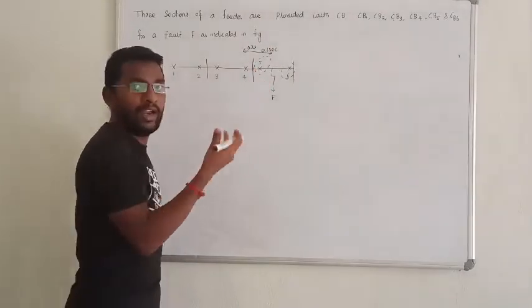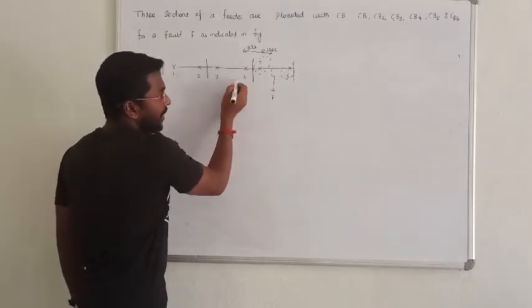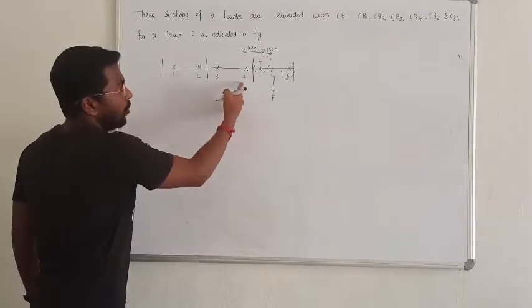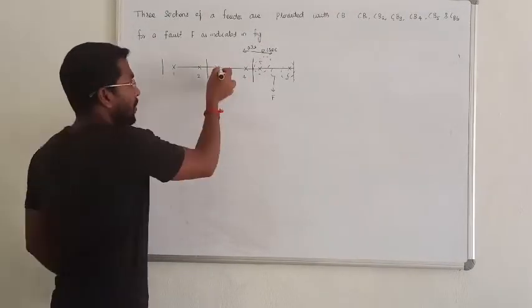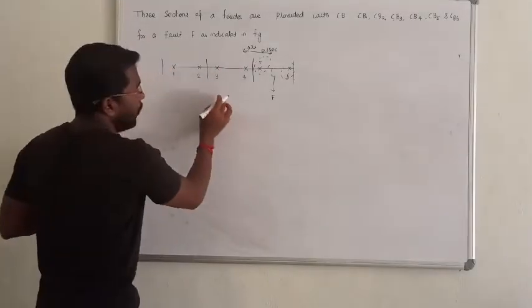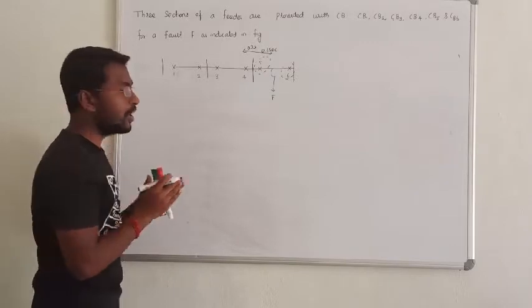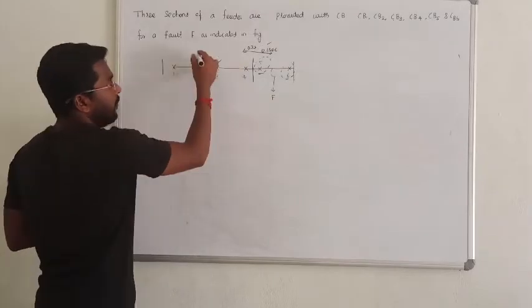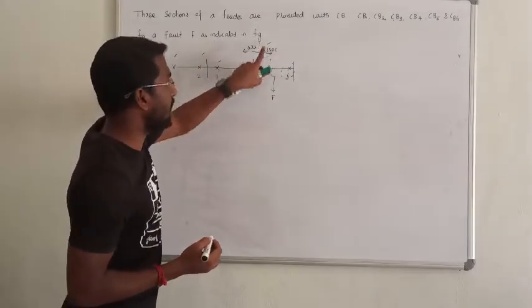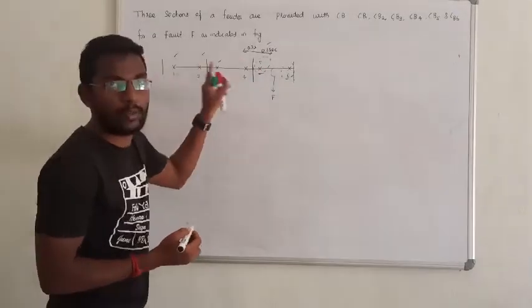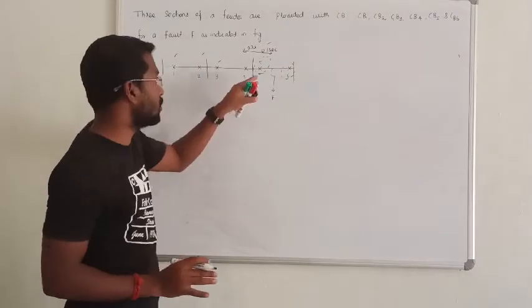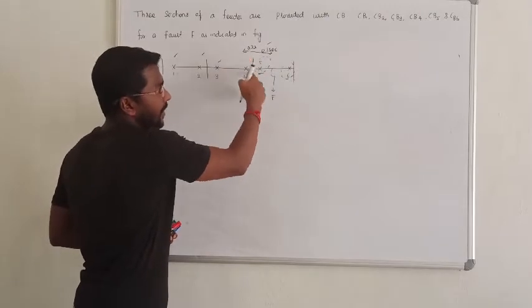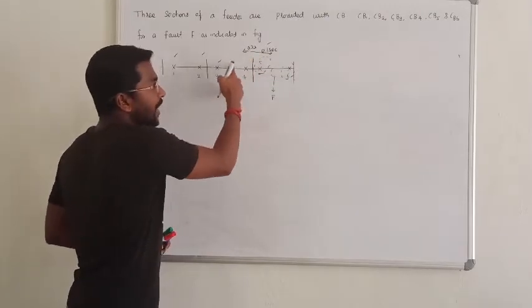If a relay fails to operate, the next relay in sequence will operate. We can set different timing for each relay - for example, the first relay at 0.1 seconds, the second at 0.3 seconds, then 0.5, 0.7, and 0.9 seconds. This creates a sequential operating system where each relay has its own assigned timing.